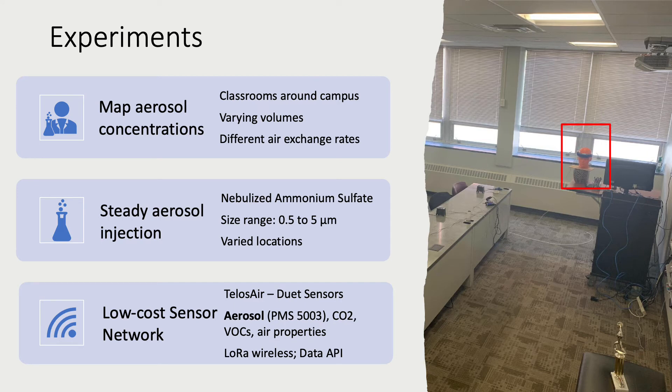We wanted to study and see if the reality is any different from that. We wanted to map aerosol concentrations in classrooms around campus with different volumes, different air exchange rates. We were mapping these concentrations from a generation source, generating at a steady rate using a nebulizer, nebulizing ammonium sulfate in that size range of interest, 500 nanometers to 5 micron. We moved the injection source from being close to the front of the room to middle and back.